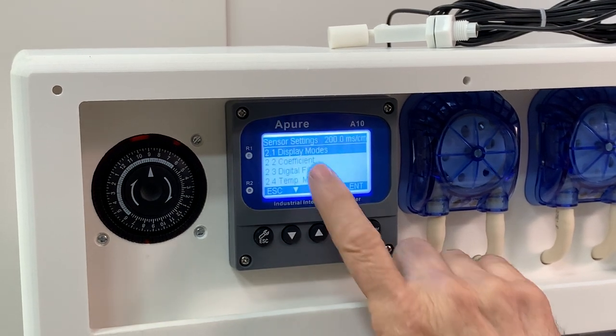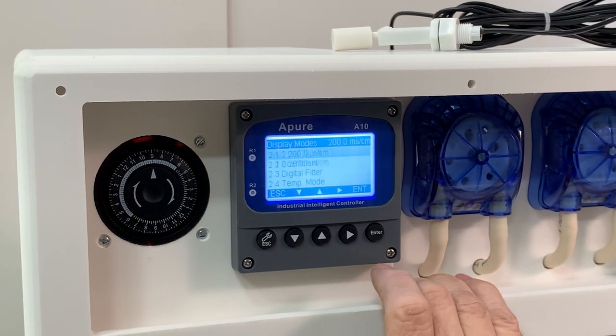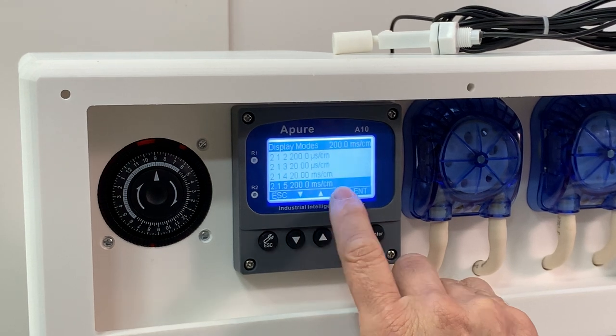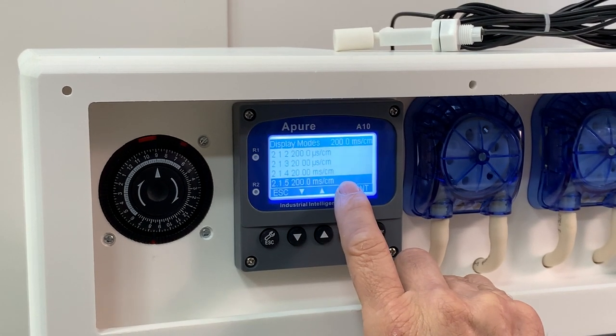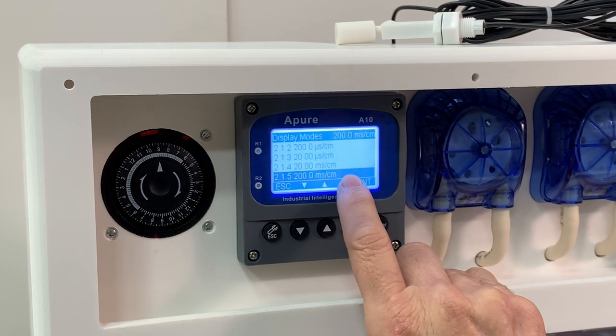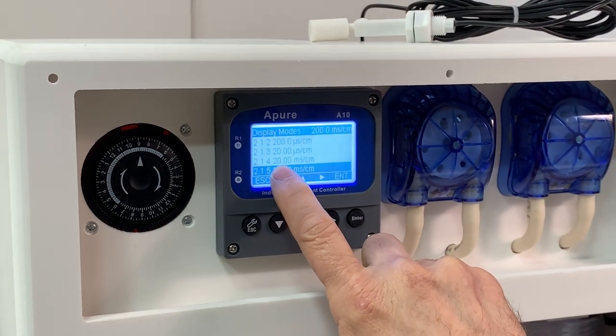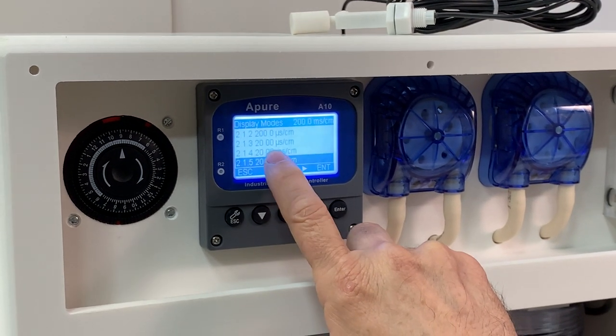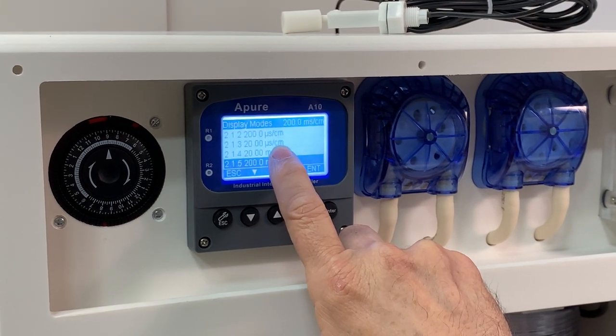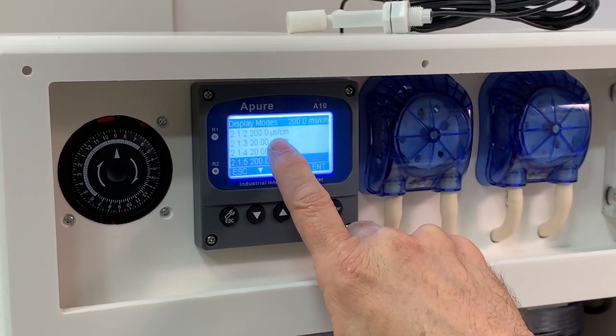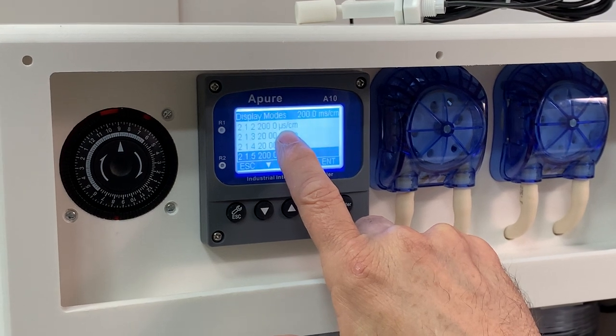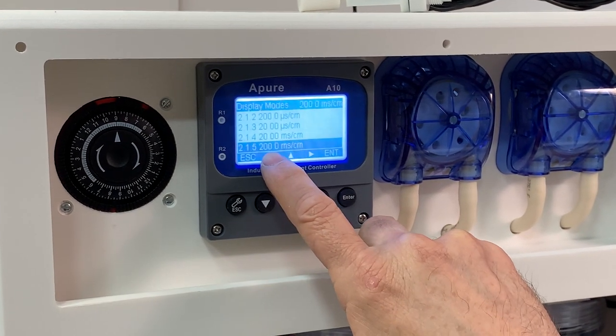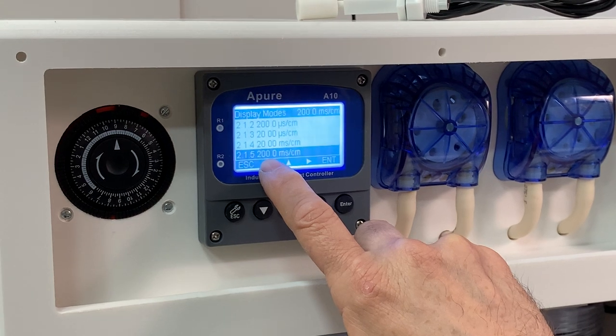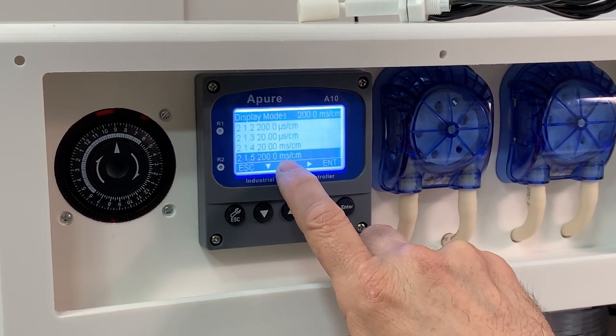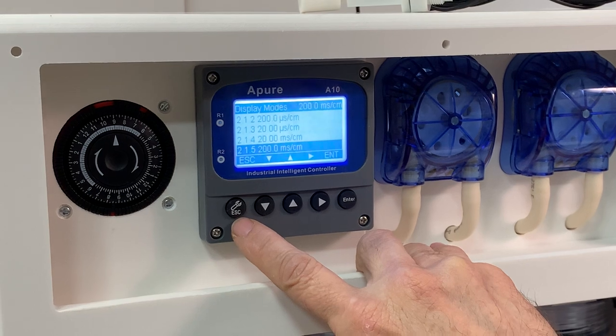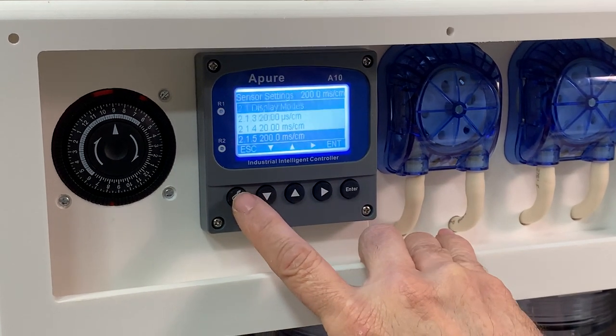I'm going to hit the enter button and it's going to say display mode. We're going to be at the 0 to 200 millisiemens because most aquariums run at 53 millisiemens. So the option above that is too low, 20 millisiemens or microsiemens would be the one below that, or 200 microsiemens. Now that's if you wanted to measure something like DI water. Since we're going to be measuring salt water, the machine's going to come set to the 200 millisiemens. Okay, so we're going to hit escape.